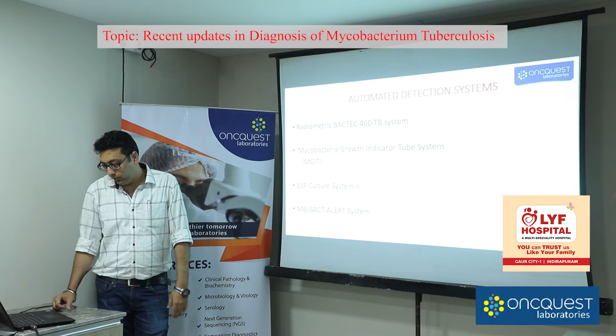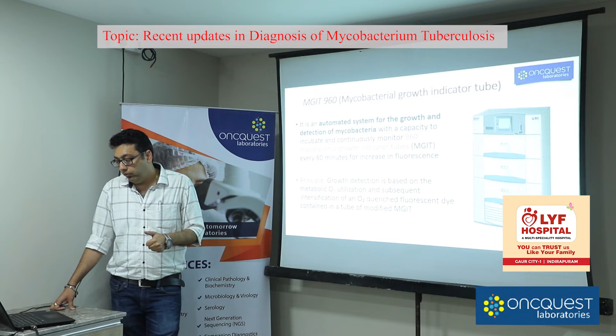Just a little bit about MGIT 960. This is the machine, how it looks. It is an automated system for growth and detection of mycobacteria, with the capacity to incubate and continuously monitor 960 mycobacteria growth indicator tubes every 60 minutes for increasing fluorescence. The principle is that growth detection is based on metabolic oxygen utilization and subsequent intensification of an oxygen quenched fluorescent dye which is contained in the tube of modified MGIT.